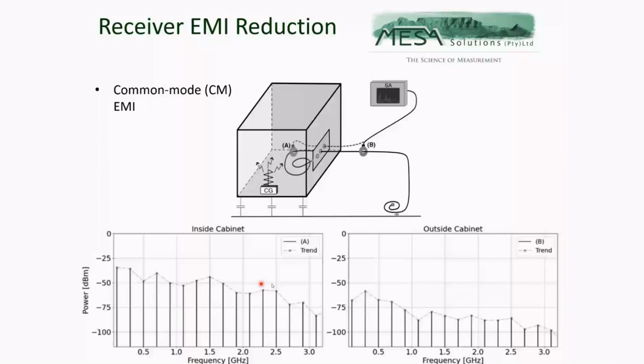But just to summarize this, if we use the radiated approach, that's energy coming directly from a spectrum analyzer, where you have no EMC cabinet, and then you have the EMC cabinet, we find shielding values of between 20 and 25 dB up to 2 gigahertz. With our comb generator approach, we find shielding values which vary, basically above 20 dB up to 3 gigahertz and more. Now, these variations depend very, very much on the cable layout.